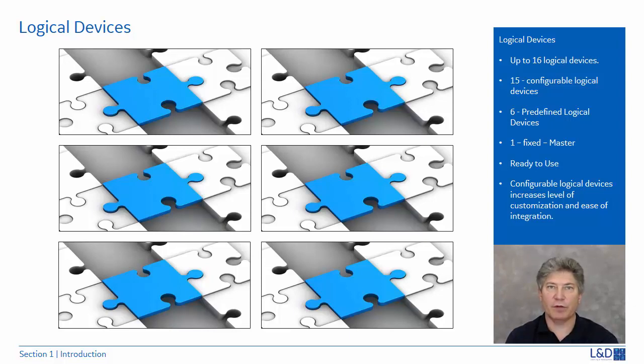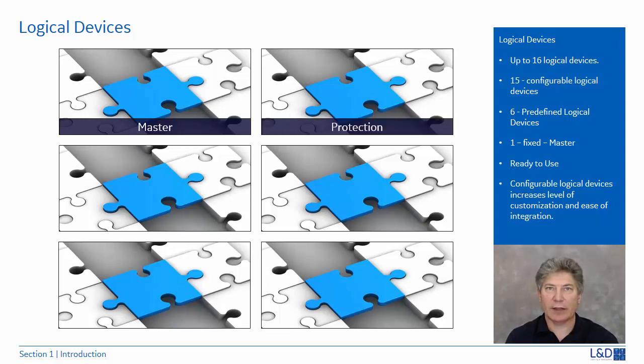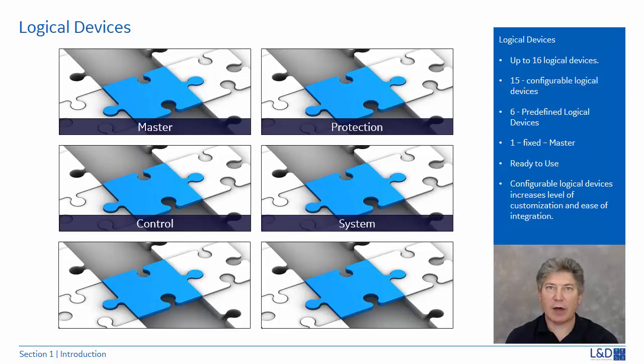Let's review the six predefined logical device categories. The first one is master, which contains the logical nodes that pertain to communications, including GOOSE, reports, remote I/O, direct I/O, virtual inputs, Modbus, DNP, and so on. The next one is protection, which contains all the protection functions. Control contains the control and monitoring functions. System contains power system devices such as breakers, switches, CTs, VTs, and so on, including interface to things such as the AC inputs, contact I/O, transducer I/O, and hard fiber I/O.